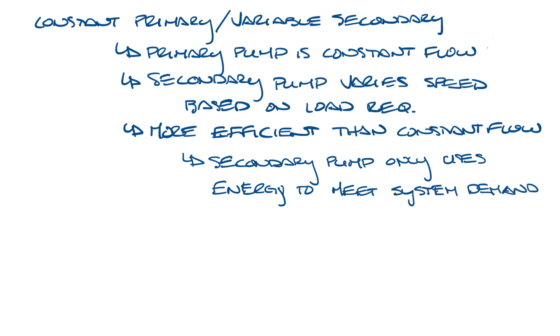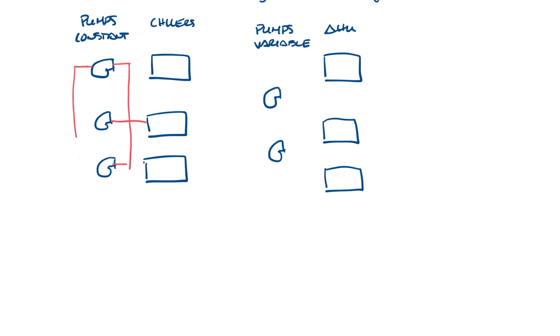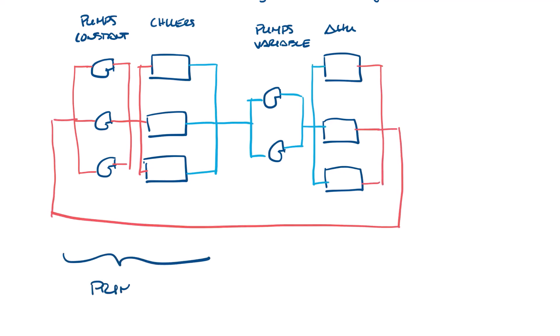Let's move this up and draw this. Let's use the same three pumps, chillers, and air handlers. But we're also going to have secondary pumps here. These are constant and these are variable. Now let's draw in the water flow and label the primary and secondary loops. The system has a bypass here, also known as the decoupler pipe, because it decouples the primary and secondary systems.